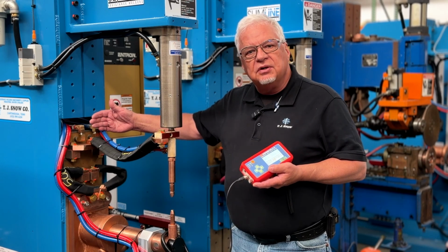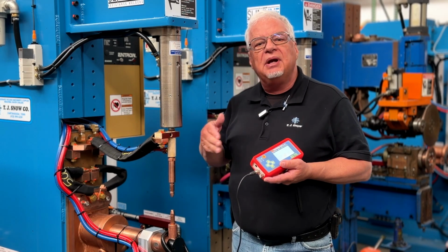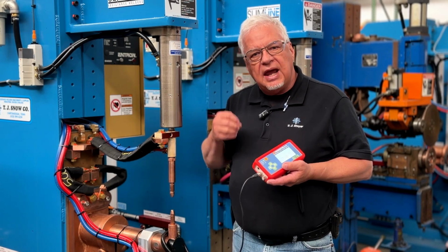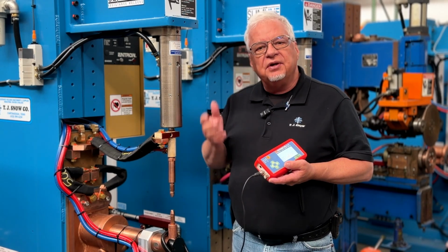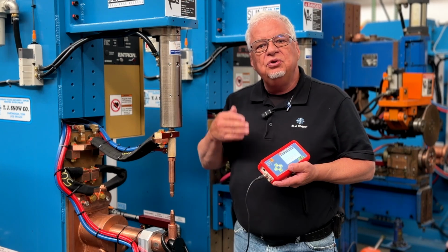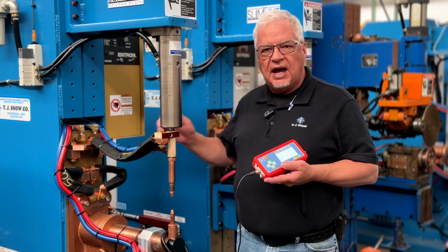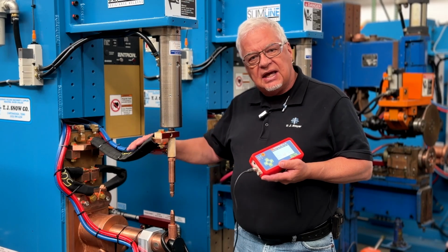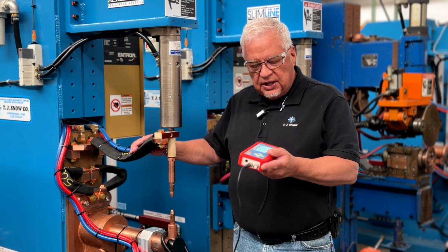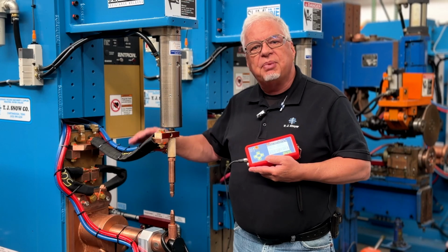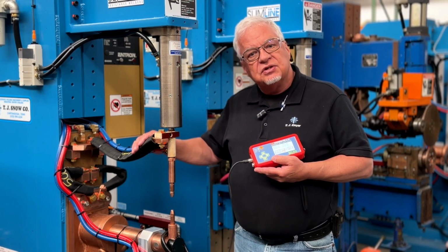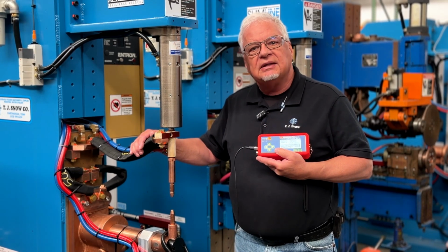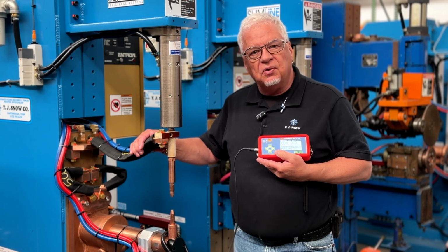Most of your weld controls are doing a primary calculation where they are taking the primary amperage and current and the turns ratio and saying you should be getting this out there. But again, it's something that you have to set that calibration with a weld scope out here at the electrodes. So there's a lot of things that can happen when you're looking at the differences in your settings.